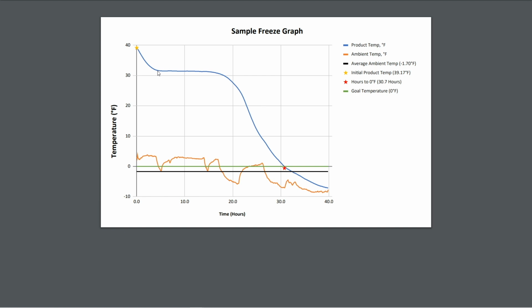Then we get into latent, and the word latent means hidden. So we're still removing heat energy from the product, but we're not seeing a temperature drop in the product until all the freezing is completed. Then we see the sensible heat below freezing falling out rather quickly. And it's really a function of the temperature difference between the ambient and the target temperature for the product. So it's especially helpful to have lower ambient temperatures when we're trying to finish that product down to our target temperature of 0. But that's kind of how you look at the heat load, and then this is a sample freeze graph. I think it can help make sense of what we're trying to do.